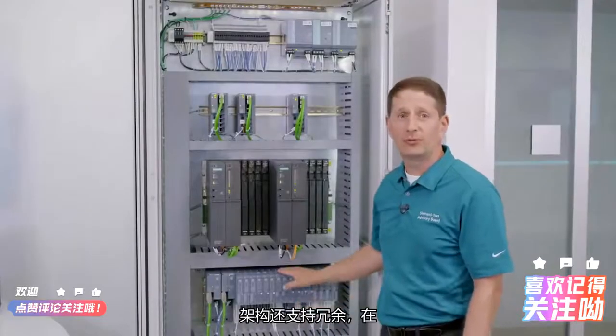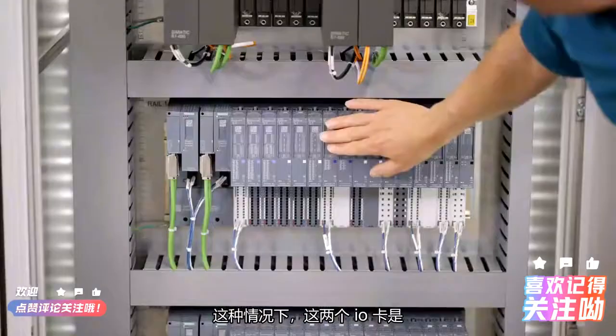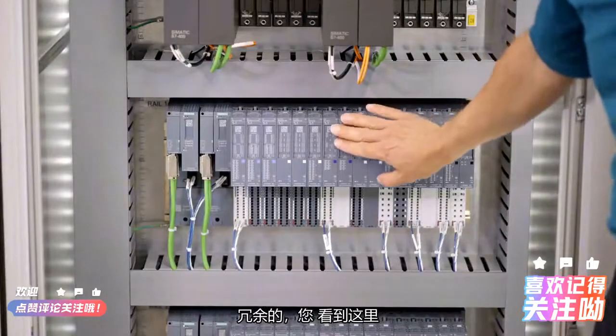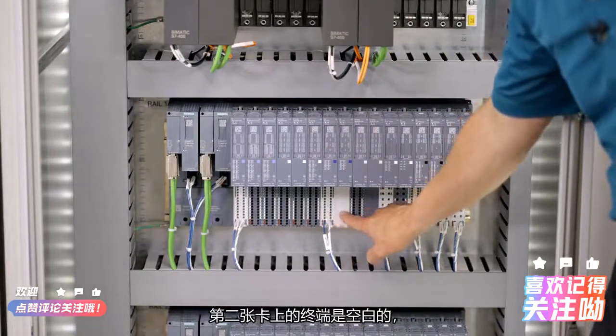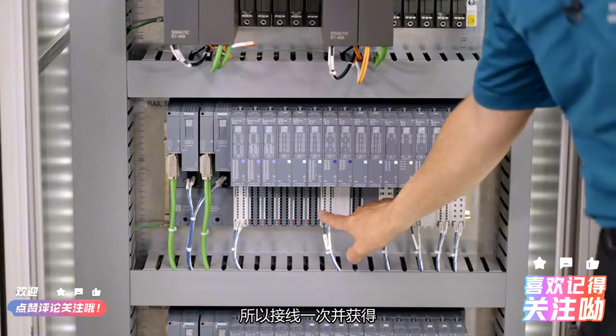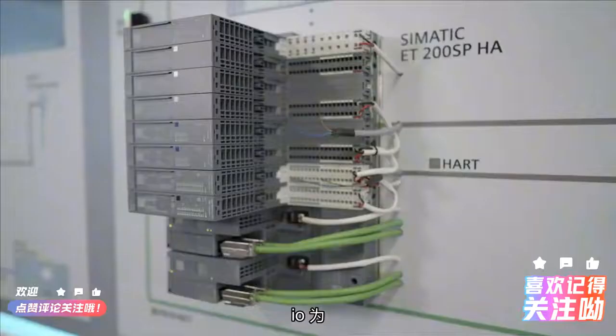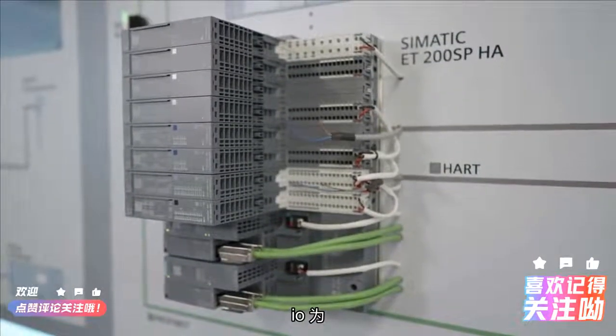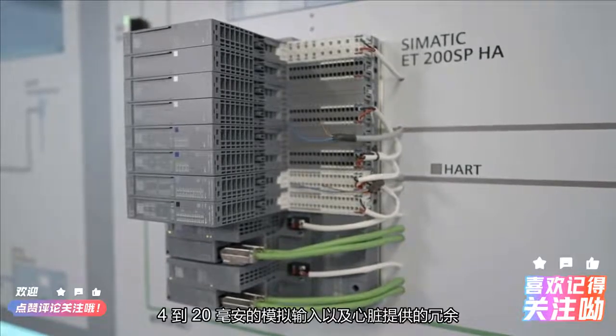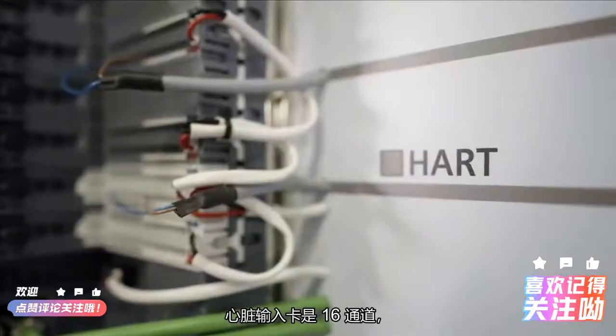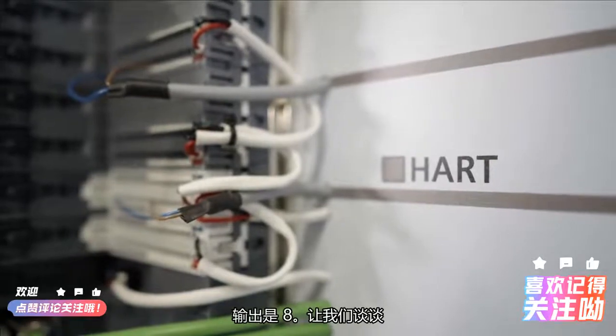The architecture also supports redundancy. In this case, these two I/O cards are redundant, and you see here the termination is blank on the second card. So wire once and get the redundancy. The I/O provides for analog inputs, both 4 to 20 milliamp as well as HART. The HART input cards are 16 channel and the outputs are 8.